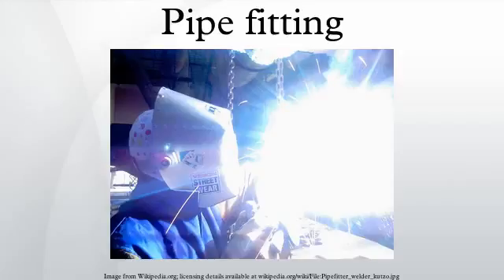Aluminium pipe. Aluminium is sometimes used due to its low cost, resistance to corrosion and solvents, and its ductility. Aluminium tube is more desirable than steel for the conveyance of flammable solvents, since it cannot create sparks when manipulated.